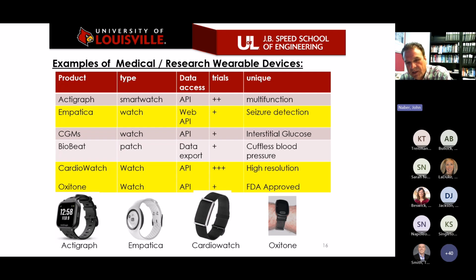Wasn't even close. So when you dig into what Oxitone does, you can see their patents, and it's a completely different design. They bring the LEDs in on the side, and they have some extra covers to keep ambient light out. So they put a lot of engineering into coming up with a better device for measuring low SpO2. If you don't need low SpO2, then there's no reason to go the FDA approval route.